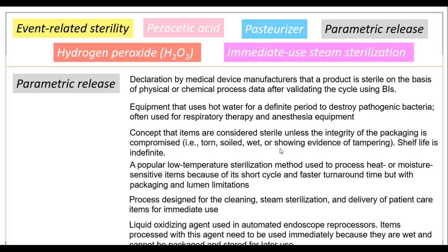Next: equipment that uses hot water for a definite period to destroy pathogenic bacteria, often used for respiratory therapy and anesthesia equipment. The hint here is respiratory therapy. Not every hospital has one — it's a pasteurizer.